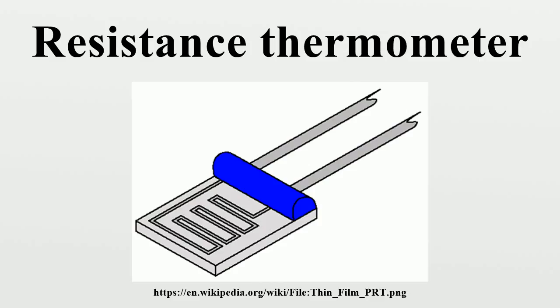Industrial PRTs are designed to withstand industrial environments. They can be almost as durable as a thermocouple. Depending on the application, industrial PRTs can use thin film elements or coil wound elements. The internal lead wires can range from PTFE insulated stranded nickel-plated copper to silver wire, depending on the sensor size and application. Sheath material is typically stainless steel. Higher temperature applications may demand Inconel. Other materials are used for specialized applications.